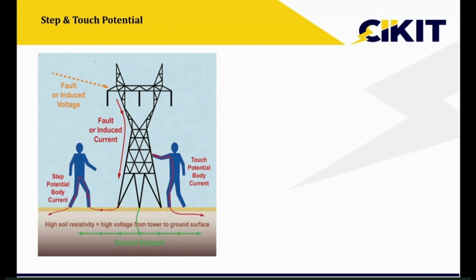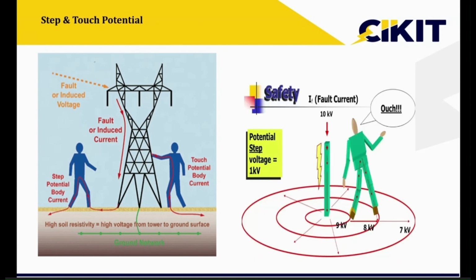Whenever the ground potential rise is happening, the two important parameters to be considered are the step and touch voltages. If any metallic structure becomes live, and I make contact by touching the structure, then because of the potential difference between the two objects, current will flow through our body. In this particular case, the body of the structure is at very high potential and our foot is at low potential. Because of this difference in potential, current will flow through our body and the person might get electrocuted. Since this damage is caused by touching the structure, it is called touch potential.